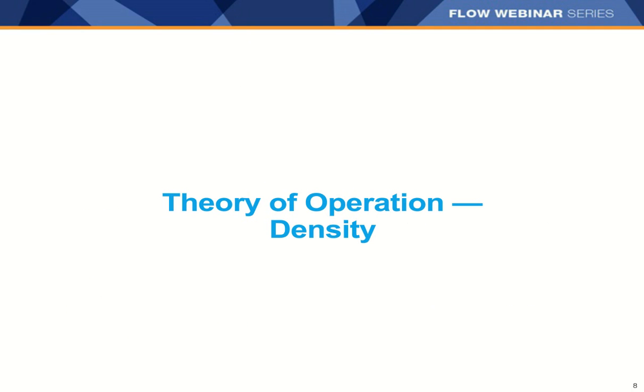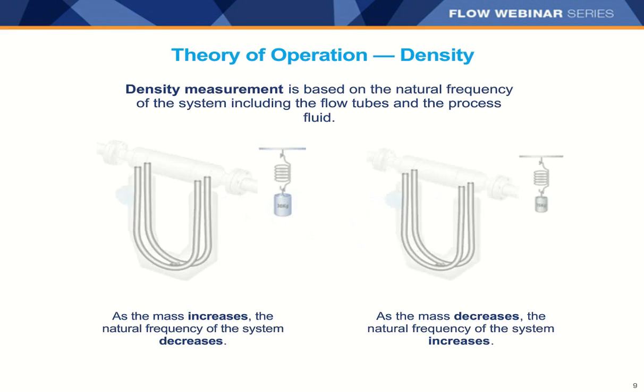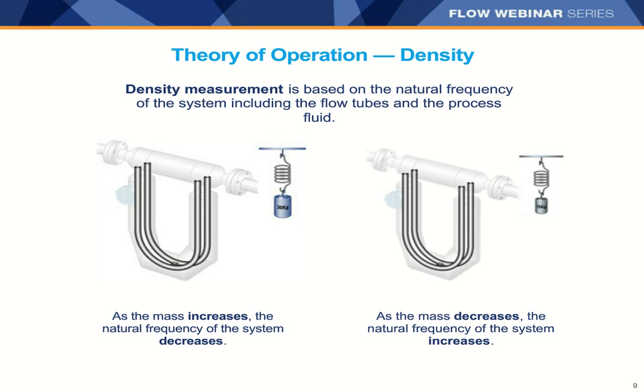Density is based on the natural frequency of the system, including the flow tubes and the process fluid. As mass increases, the natural frequency decreases; as mass decreases, the natural frequency increases. If something very dense comes through the tubes, it slows the frequency down; something with less density speeds the frequency up. It's an inverse relationship.